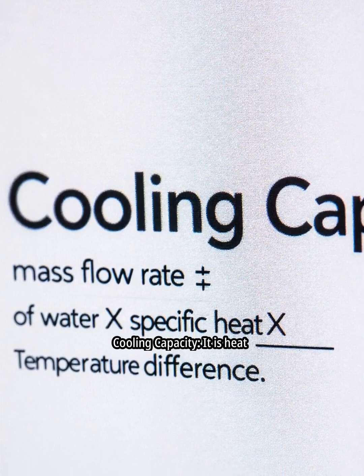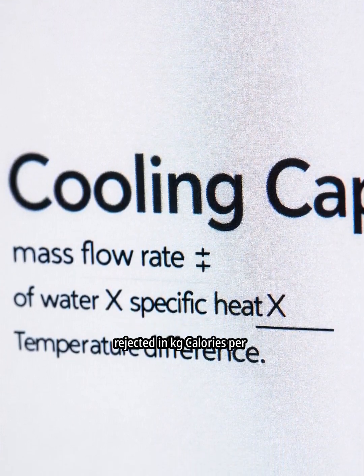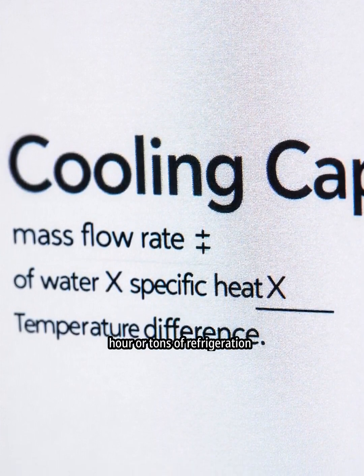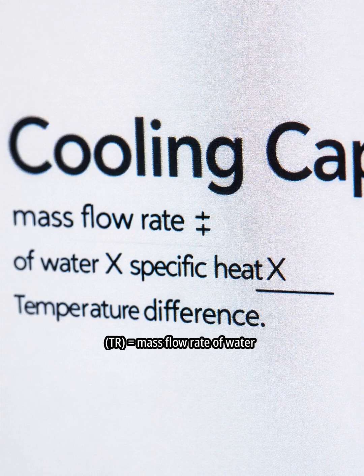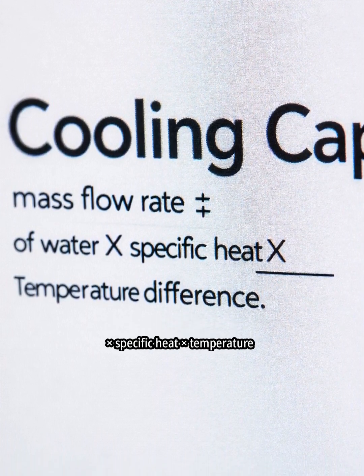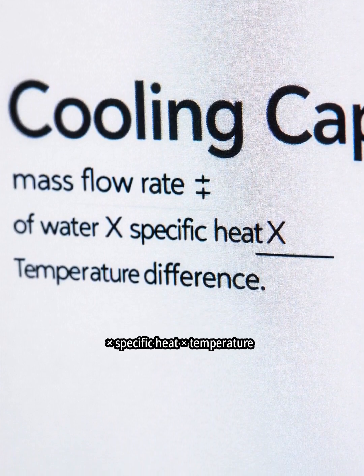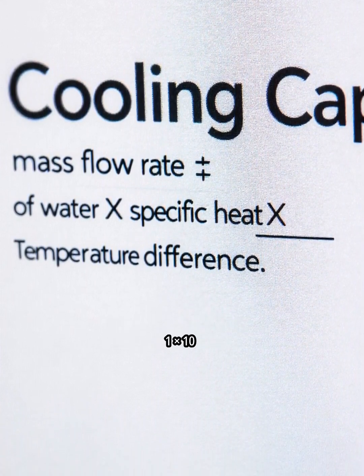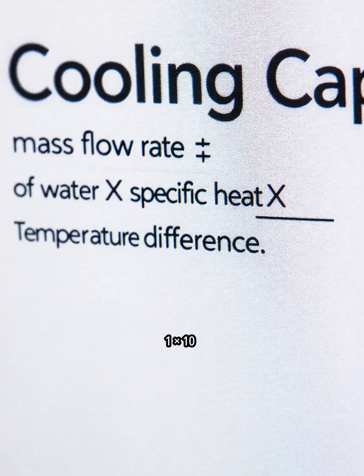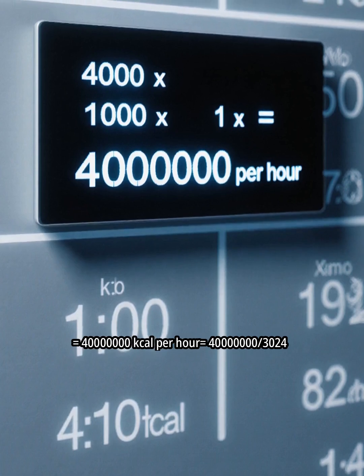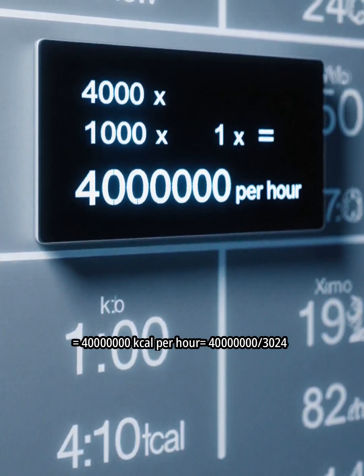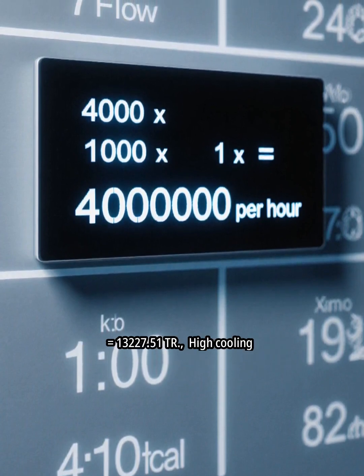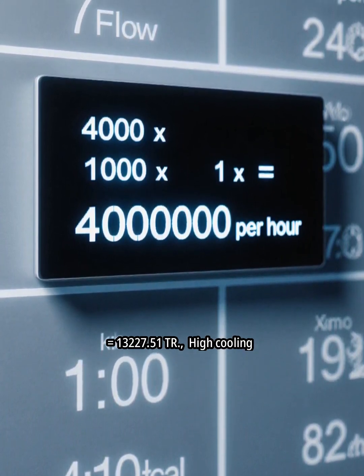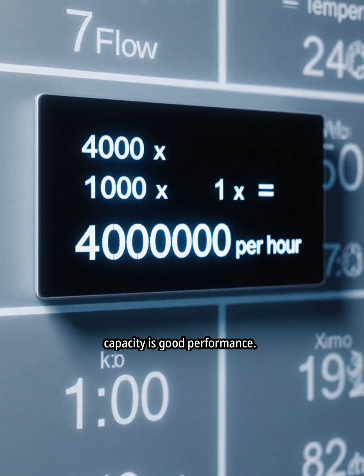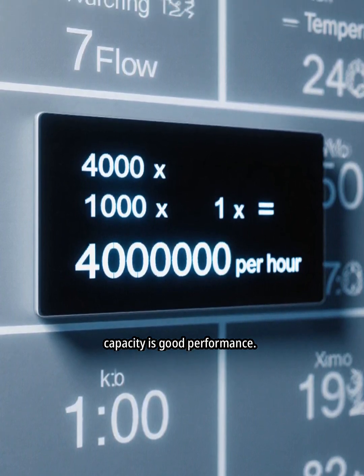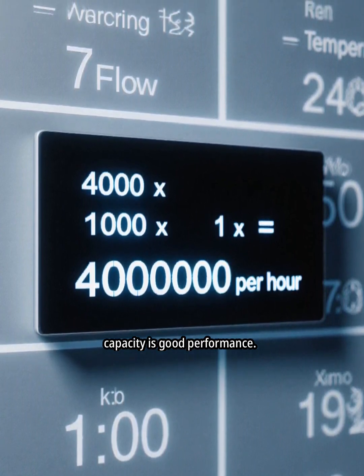Cooling capacity. It is heat rejected in kilocalories per hour, or tons of refrigeration. TR equals mass flow rate of water times specific heat times temperature difference. 4,000 times 1,000 times 1 times 10 equals 40 million kilocalories per hour. 40,000,000 divided by 3,024 equals 13,227.51 TR. High cooling capacity is good performance.